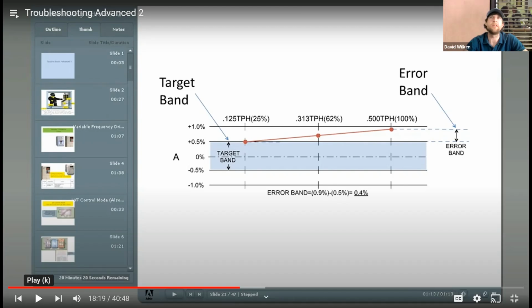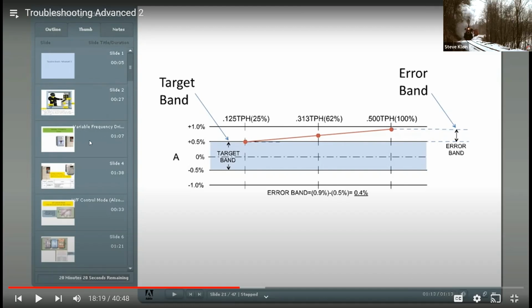We deal with venting sometimes in asphalt dust systems. So if you're blowing the material, we always recommend venting. Some people don't think there's pressure that comes up out of the airlock below it, but some people do think there is, and we're one of those people. As material's going down the vanes, air is coming back up the return vanes. So pressurizing your scale is going to affect your scale reading. It can also blow material out into your J box, and now you're getting filled up under your load cell. Those are kind of issues people don't see until they become issues.